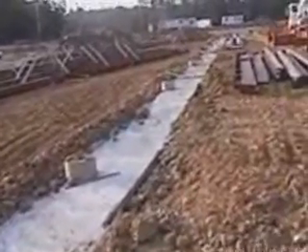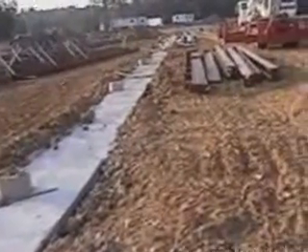This is the foundation that separates the rink environment from the actual core. You can see how the foundation's broken here, and the reason for that is we have to run the transmission lines from the rink floor system out into the area where the rink is. Always remember that either a form-out or a sleeve arrangement has to be created to coordinate with the needs of the rink contractor installing the rink floor.